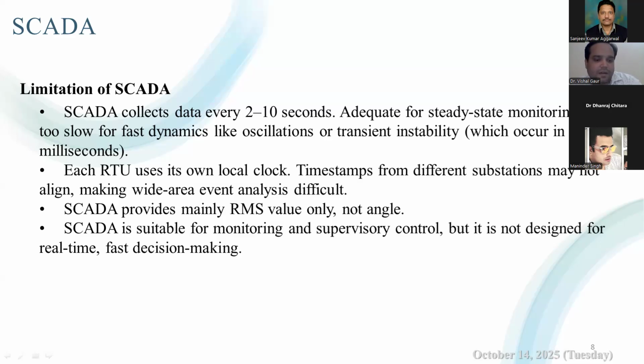Third, SCADA mainly provides the RMS values of voltage and current. These values are good for steady state, but not for faults and disturbances, where we also require angle information. Fourth, SCADA is suitable for monitoring and supervisory control, but it is not designed for real-time fast decision making. This limitation is exactly what pushed the development of WAMS and synchrophasors. So all these are the limitations of SCADA, and because of that we have moved towards WAMS, or synchrophasors.